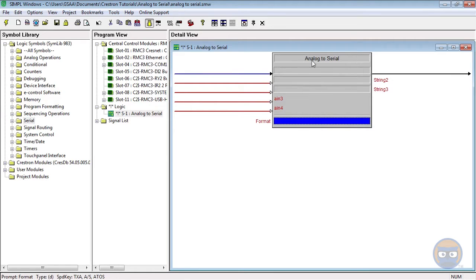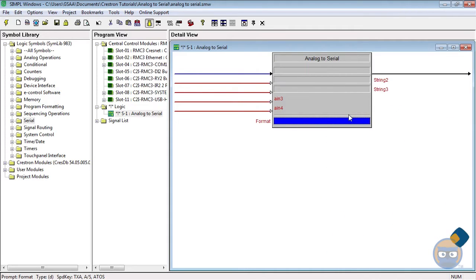If you ever need to use one of these symbols, you'll probably want to have an ASCII table handy. There are two things to keep in mind: the output string isn't created until the trig input goes high, and the format 256D is the most commonly used. It translates numbers into their ASCII equivalents.